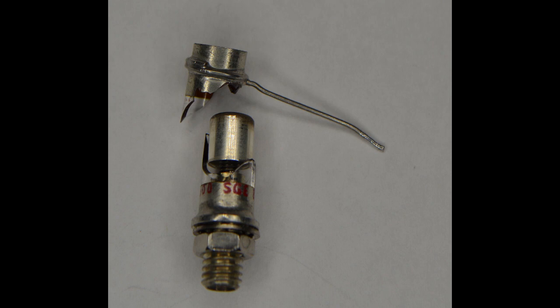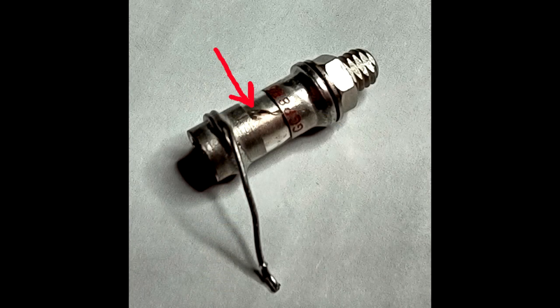The capacitor consists of a glass cylinder with a movable slug inside and a conductive coating on the outside. I broke one to see the construction in more detail. The slug appears to be silver-plated and is tarnished on the exposed top. The first capacitor I removed had a couple of visible cracks and a spot of tarnish on the slug underneath the crack. The leakage could be occurring through the crack. The other two capacitors had no visible cracks but were nevertheless faulty. I don't claim to understand the failure mechanism, particularly since the dielectric is glass in this case, but it was possibly induced by voltages over 1000 on the input and breakdown in the capacitors.